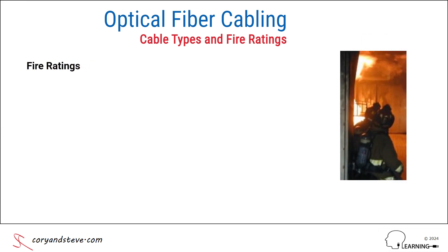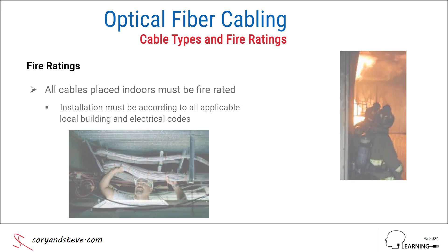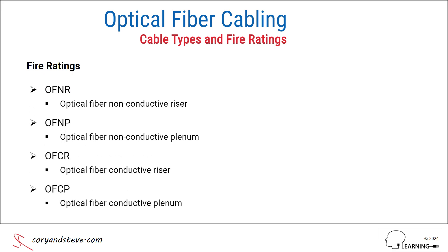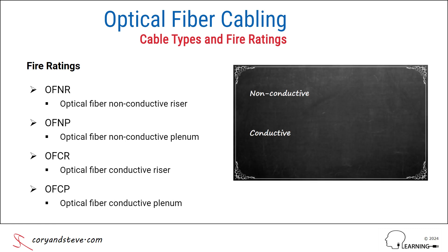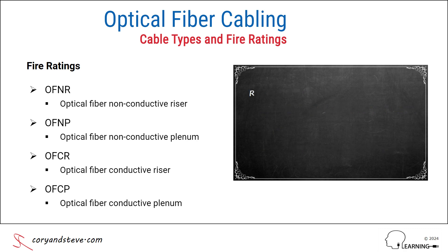Next, we'll summarize the fire ratings for indoor-only and indoor-outdoor fiber cables. In order to help prevent the rapid spread of fire within buildings, all indoor or indoor-outdoor cables, including optical fiber ones, must be fire rated and installed according to all applicable local building and electrical codes. There are four designations for optical fiber cabling: OFNR, OFNP, OFCR, and OFCP. Non-conductive or conductive refers to the absence or presence of any metallic elements in the cable. For example, an armored optical fiber cable or a composite cable containing both fibers and twisted pairs would both be classified as conductive.